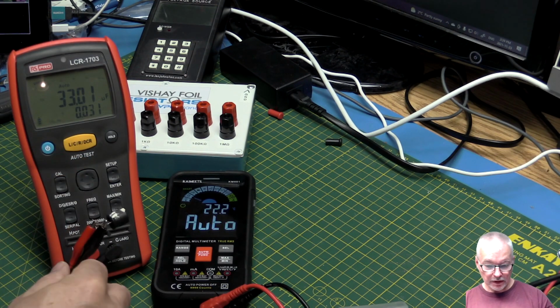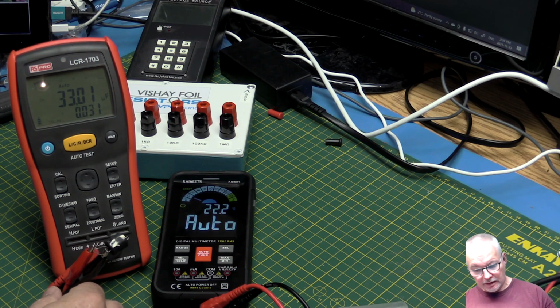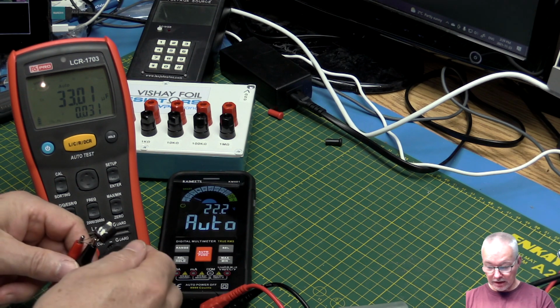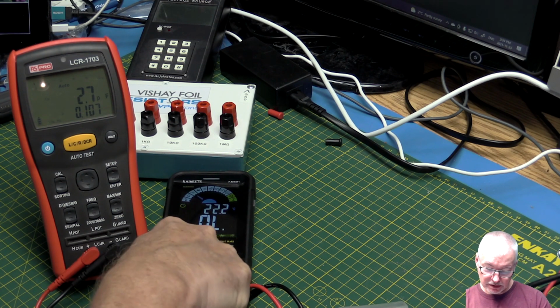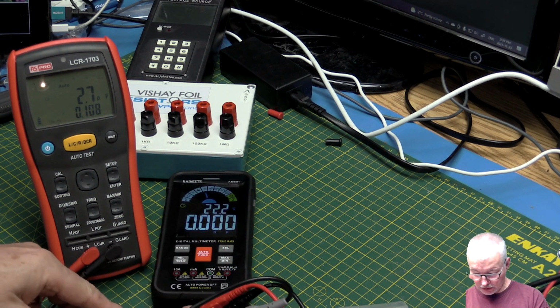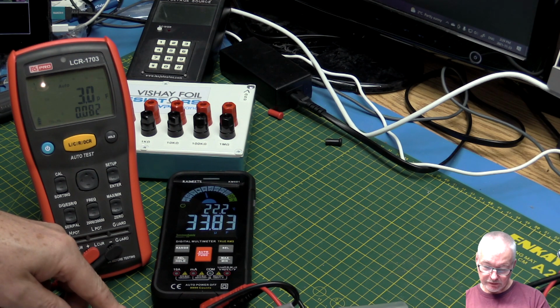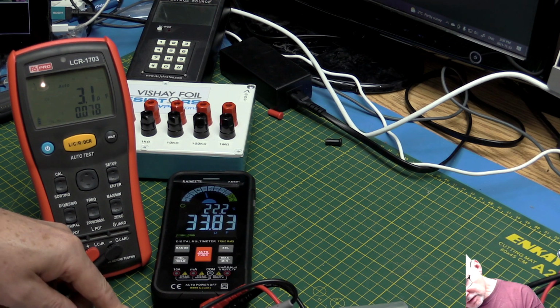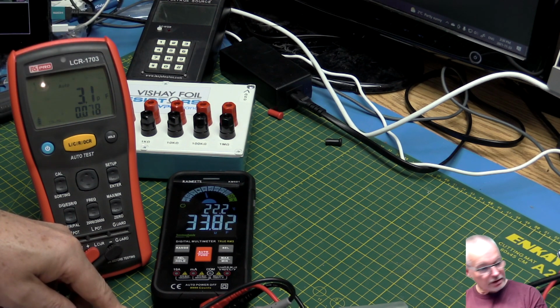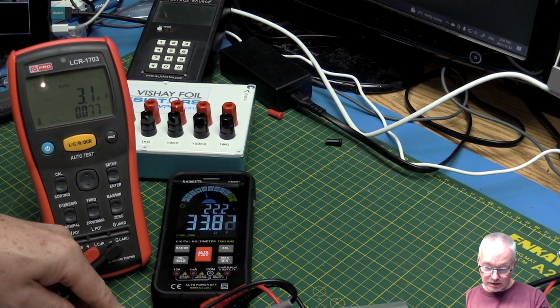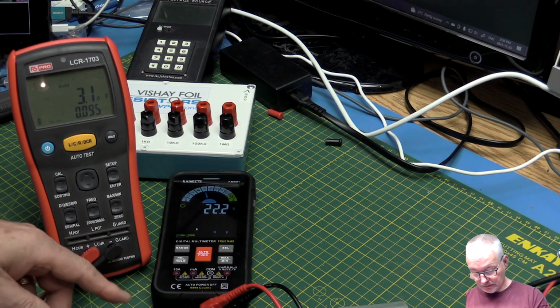First up, we've got a 33.0 microfarad cap. Let's see what the meter reads, because we need to set it to capacitance. That's not within its auto ranging. So 33.85 - the other meter read 33. Probably some variances with frequency that it's using. I think the LCR meter is currently set to 120 Hertz. The Kaiweets KM601 could be using a completely different frequency, so it's still within specifications anyway. It's reading 33.8 microfarads, so that's good - first success.